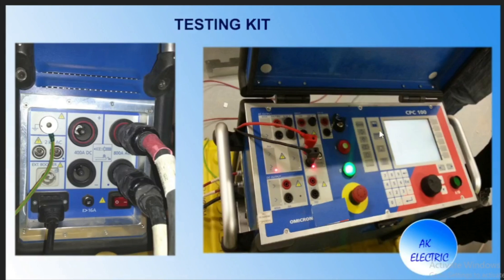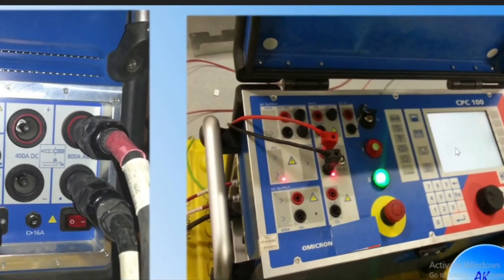This is another testing kit used for MCB trip test called CPC100. Here up to 800 ampere AC you can inject for MCB — these two cables should be connected to the MCB poles. Using the quick option, the MCB trip test main page will open where you can select whatever current you want to inject — whether 100, 200, or 300 ampere. After selecting, press start; the MCB will trip according to its trip characteristics and you will get the injected current value and trip time displayed. This is also a good testing kit for MCB trip test.